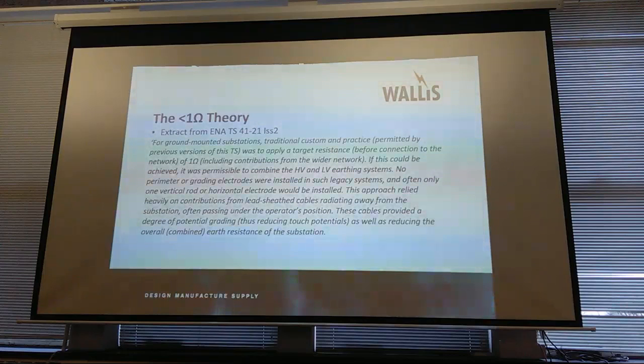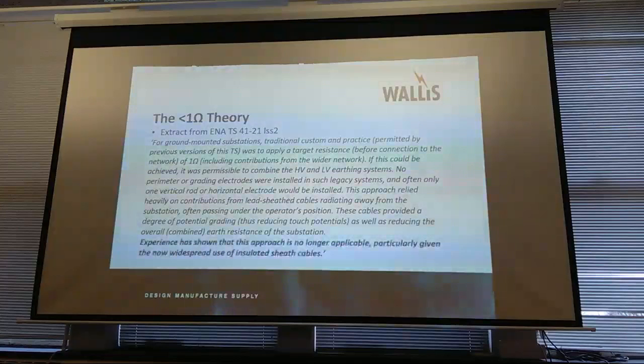the cables provide a degree of potential gradient, thus reducing, as well as, I think, there you go. Experience has shown that this approach is no longer applicable, particularly given the now widespread use of insulated sheath cables. So it's there, it's documented. ENA TS 41-21 Iss2 says that this approach is no longer applicable. So when you're coming across this less than 1 ohm earth, it's got to start you thinking a little bit.